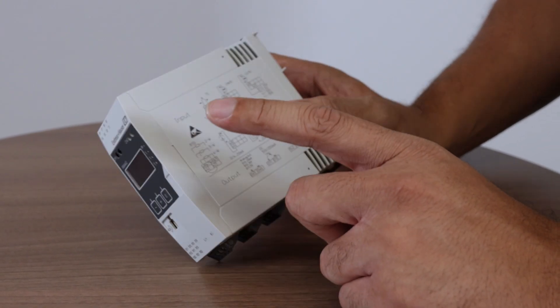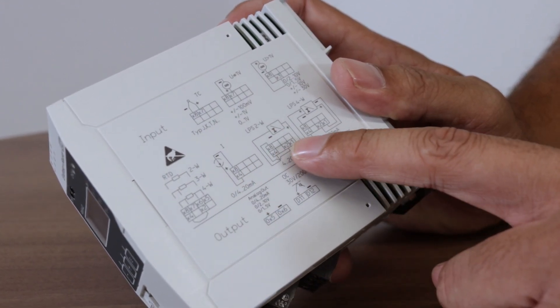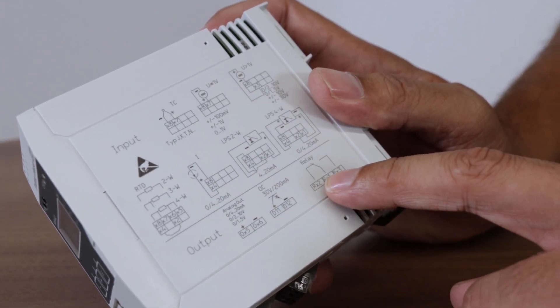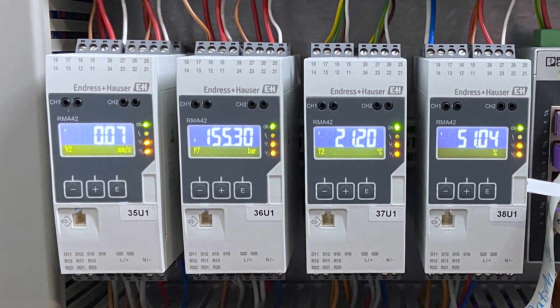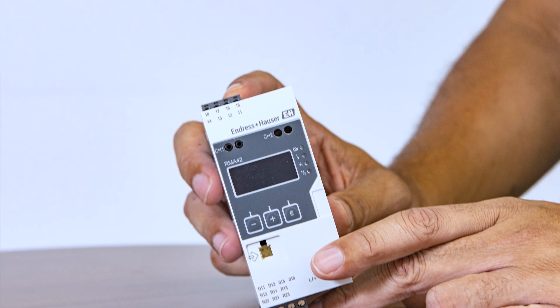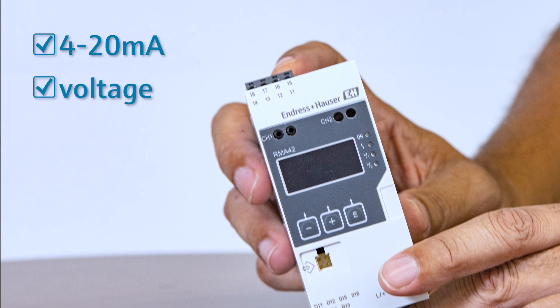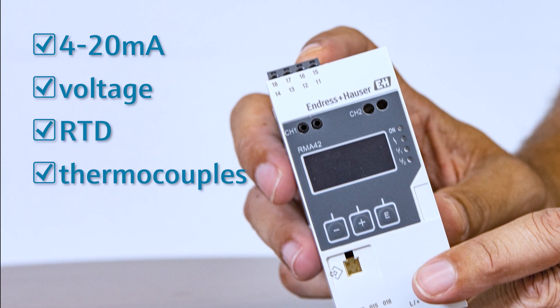The device is available with one or two universal inputs and analog outputs and with two integrated relays. With the integrated loop power supply, a two-wire sensor like for instance the Picomag flow meter can be powered. The universal inputs enable the connection of 4-20mA signals, voltage, RTDs and thermocouples.